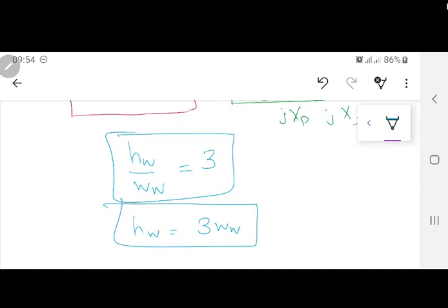So this method which is being used by this book, in which you are having the height of the window fixed, is a little difficult to adjust, because now you have constraints. You have already constrained it, and if you have not kept more height than this, then what will you do in that case? Okay, you will say it is not fitting in one layer, so what we do is change the conductor size and something like that. If it was a conductor like this one, square shape, maybe you can have a rectangular shape. That will change the orientation of the whole winding.